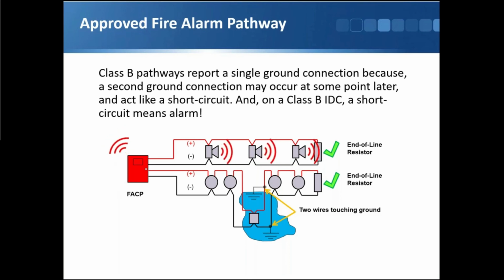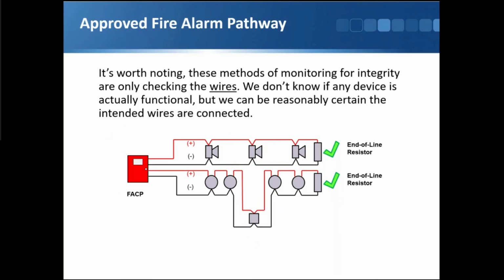So that is what you're all familiar with. But this is another point that I want to make here, is that all of this is reporting that the devices, the wiring to the devices is intact. We still don't require the individual components to report back that, hey, I'm okay, I'm working fine, which would be possible in today's new SLC technology.